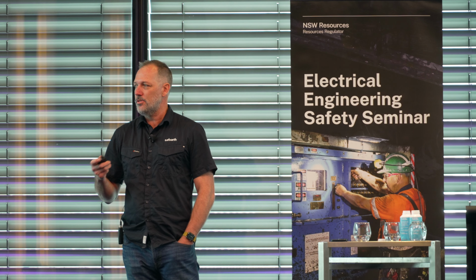More recently, at another site, they're saying no, we won't let you connect, and they don't have a good justification why. They just feel it's written in their design standard that you've really got to prove it to them. These NSPs have got to be careful when they make these statements, because under work health and safety legislation we're bound to eliminate hazards, and if we can't eliminate them, reduce the risk to as low as reasonably practicable. If they mandate these isolations, they're creating higher risk - so due to a policy they're enforcing higher risk upon you, which doesn't work with the legislation. I feel like it's going to bite them one day when a foreseeable incident happens and they try to say it was written in their guide that you can't bond. That's not good enough - it's got to be engineered properly.